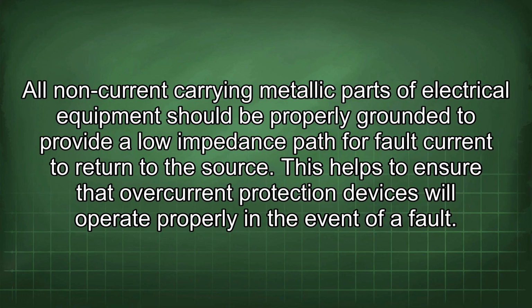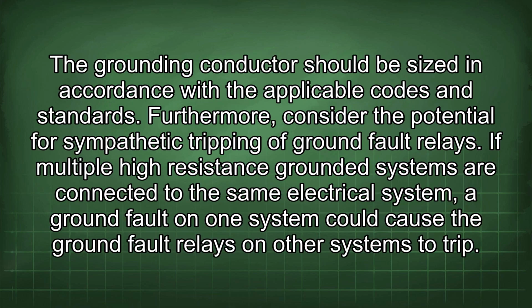All non-current carrying metallic parts of electrical equipment should be properly grounded to provide a low impedance path for fault current to return to the source. This helps to ensure that overcurrent protection devices will operate properly in the event of a fault. The grounding conductor should be sized in accordance with the applicable codes and standards.